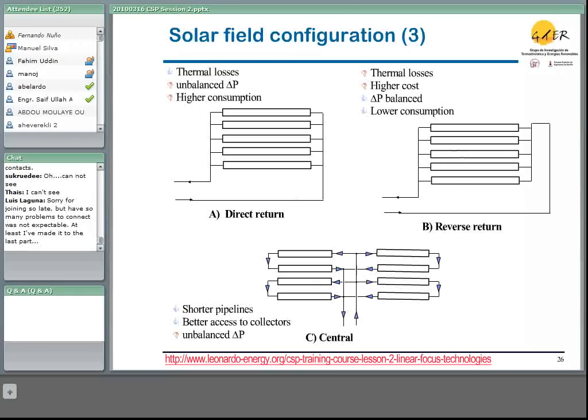The reverse return connection has a better pressure drop balance and lower consumption, but the cost is higher and the thermal losses increase compared to the direct return connection. And finally, the central connection is probably the best option especially for large solar fields, because you have shorter pipelines and better access to collectors. Although you have unbalanced pressure drops, and you have to compensate with valves and so on to make sure that you have the adequate mass flow at the field.